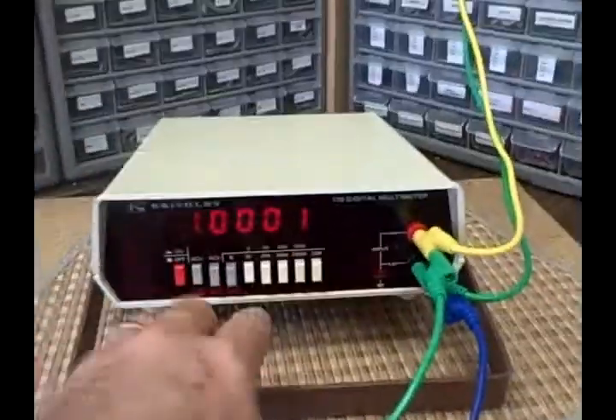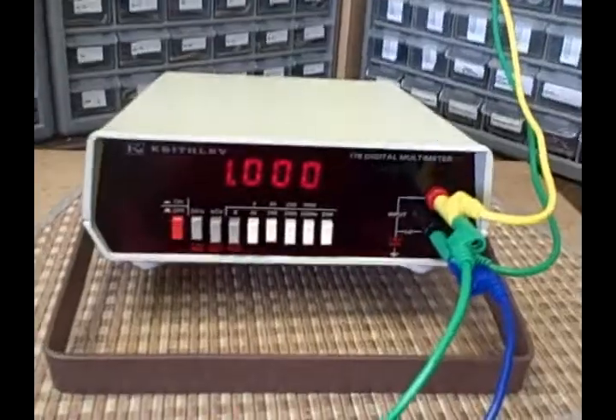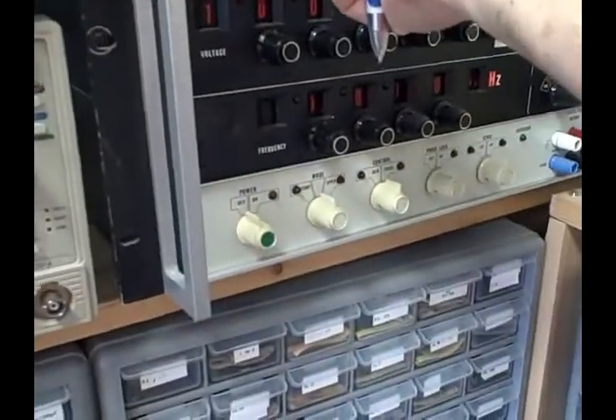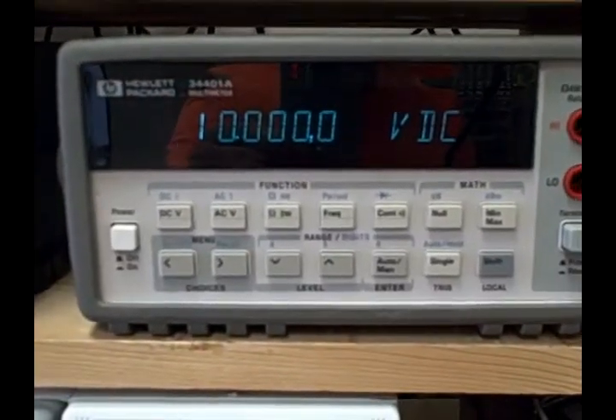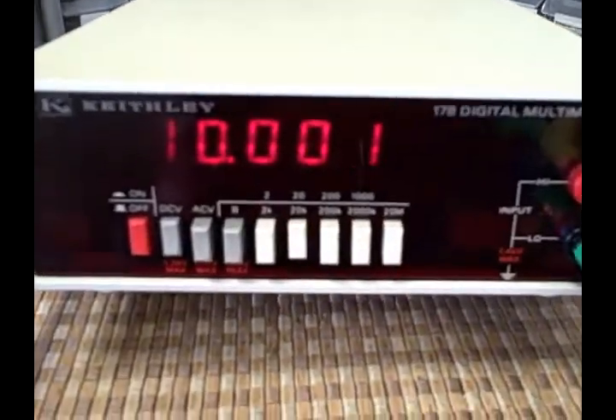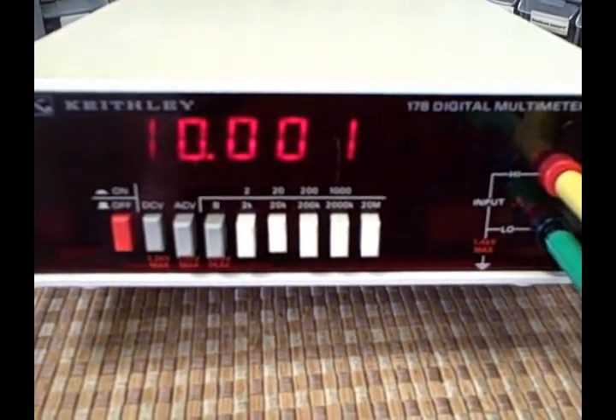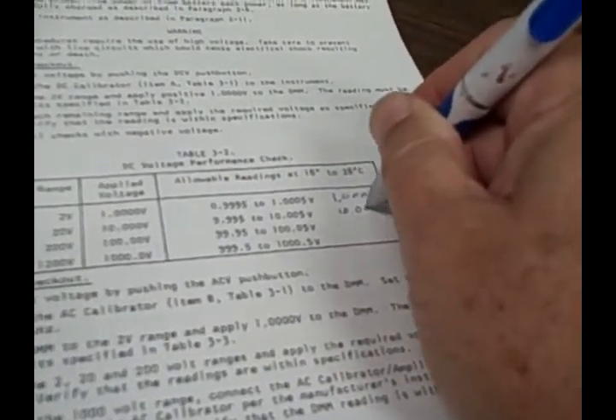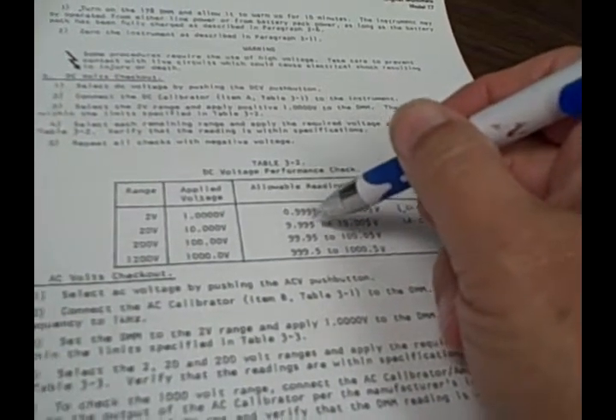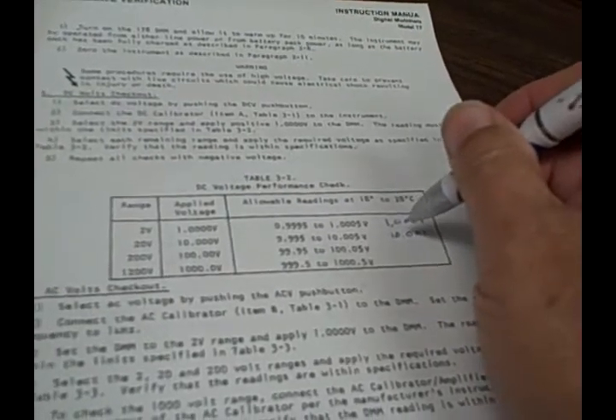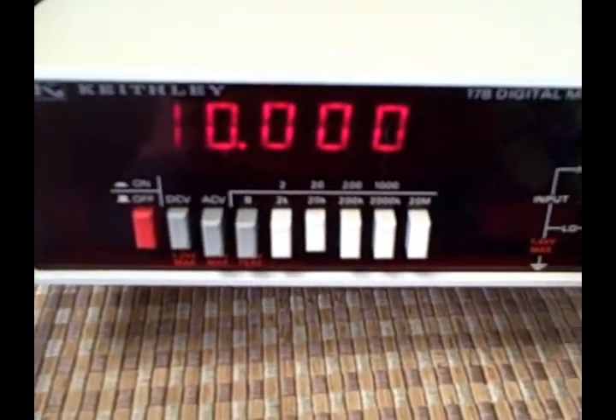We're going to go to the 20 volt range next. Still maintain the 1.000, which is good. And we want to go to 10 volts. We have 10.000 on the Hewlett-Packard, and we are reading 10.00, and it's a 0 or a 1. So we're going to write down the 1, that's the worst case. 10.001. We are considered good if we're between 9.995 to 10.005. And of course at 10.001 we are a millivolt off of perfect, and we're right in the middle. So again, 20 volt scale performance is excellent. We're within the 0.04%. In fact, we've settled more at the 0 than at the 1.